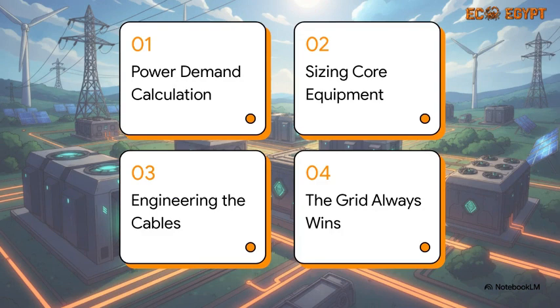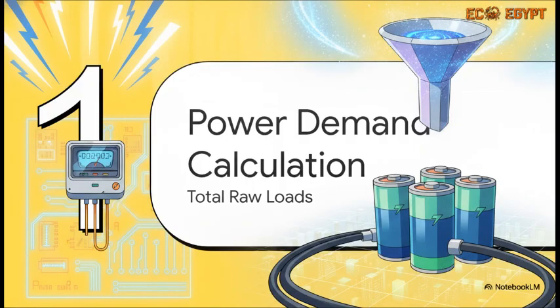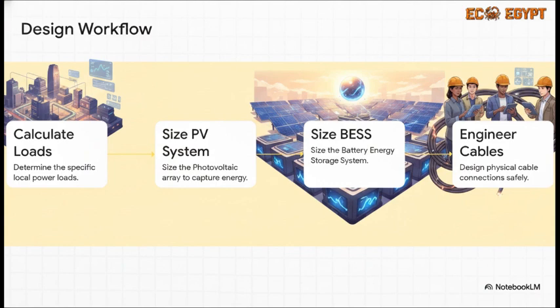So here is our roadmap for today. Calculating the power demand, sizing the core equipment, engineering the cables, and finally, why the grid always wins. All right, let's jump straight into section 1, calculating the power demand. Now, a traditional engineering workflow usually moves pretty logically. You calculate your specific local loads, you size the solar system to capture the energy, you size your battery energy storage system, the BESS, to hold it, and then you engineer the cables. Makes total sense, right? Well, utility-scale projects flip this entire sequence on its head.